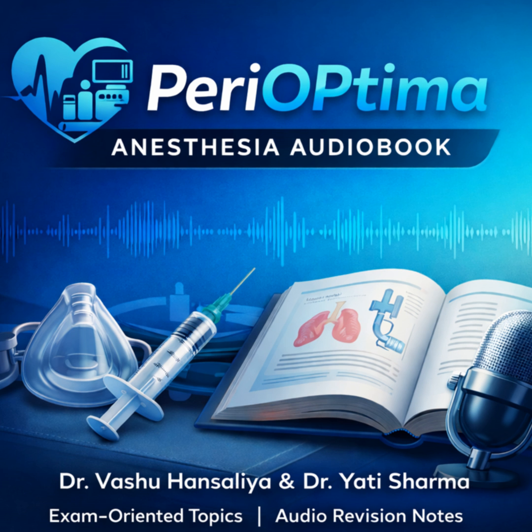And pop the cuff? It'll either burst the cuff or, more commonly, it will cause a weak spot to balloon out, creating a herniation. If you're in a Viva and the examiner hands you an LMA with a little bubble on the cuff, they know you don't understand the practicalities of autoclaving. It's a great tip. What about our anesthesia circuits?